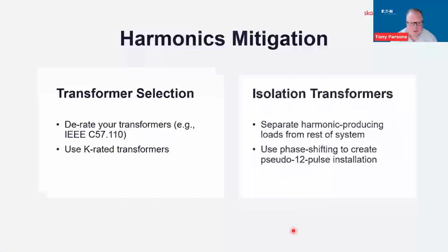As far as dealing with transformer heating, again, transformer selection can be important in the U.S., or if you're dealing with IEEE standards on your equipment. There is IEEE C57.110, a standard that talks about how to essentially derate your transformers for harmonic loading. And I think Steve gave a reference that the rest of you may use for similar things. In the US, we also have K-rated or K-factor rated transformers. The K-factor is very closely related to that FHL that he showed. And so essentially using transformers designed for the harmonic levels that they may see.